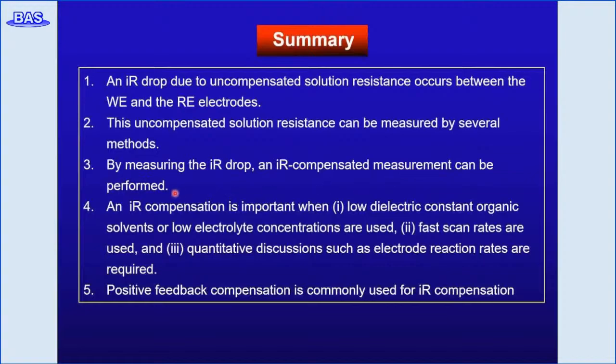In particular cases, such as low dielectric constant organic solvents, low electrolyte concentration, or high scan rate, and when quantitative discussions such as electroreaction rate are needed, IR compensation is necessary. Positive feedback compensation is commonly used for IR compensation. However, be careful of circuit oscillations.